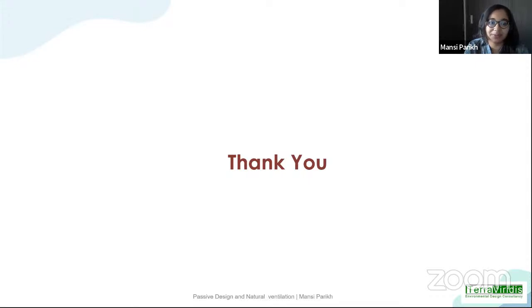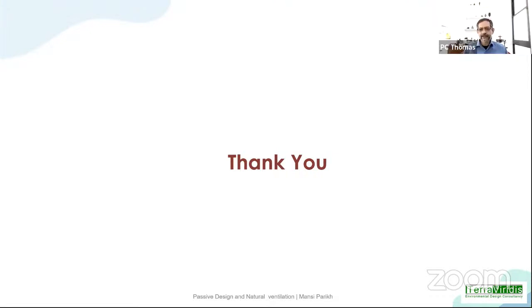LPD you can get from the ECBC manual, but equipment, I would say we'll have to do a little bit of market survey, as you said, PC. We did that for this particular project. And I saw some numbers: you had one desktop per 12 square meters, and the equipment numbers are for that sort of occupation density. Yeah.